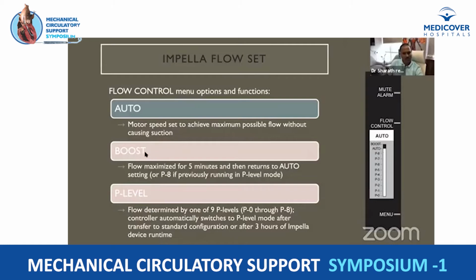And we have another option, boost, wherein we can quickly increase to maximum flow, which stays for 5 minutes, and then it goes back to auto setting or your P level flow. So these are the various P level flow rates in an Impella CP catheter. P0 is no flow, P1 is 0 to 1.7 liters. It all depends on patient volume status, position of the Impella, and also pressure. P2 is 1 to 2.1, and P8 is basically 3 to 3.3 liters.